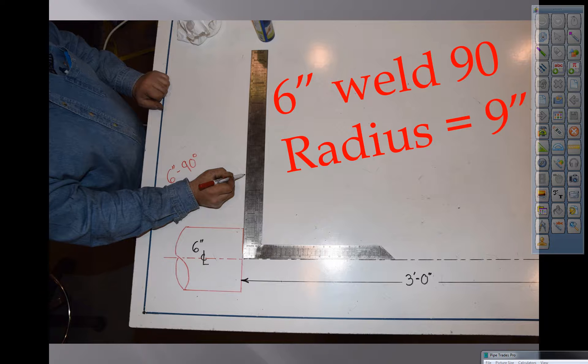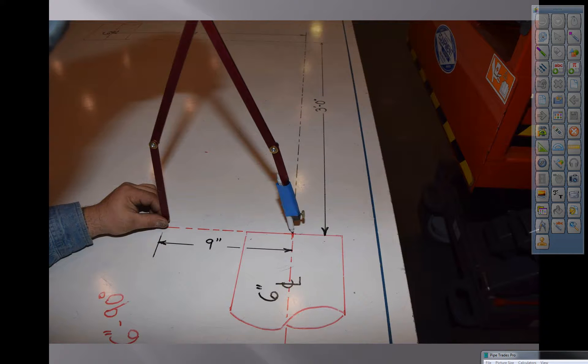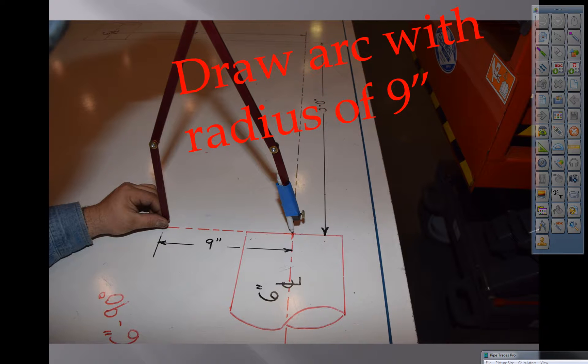So anytime we have problems like this, we're looking for some information that we know, and this is predetermined by the manufacturer. So a six inch weld 90 has a radius of nine inches, or the takeoff is nine inches. So you see our square is perpendicular to our black dotted line. And put a dot there at nine inches. Now we're going to draw an arc with the radius of nine inches, going from that vertex there.